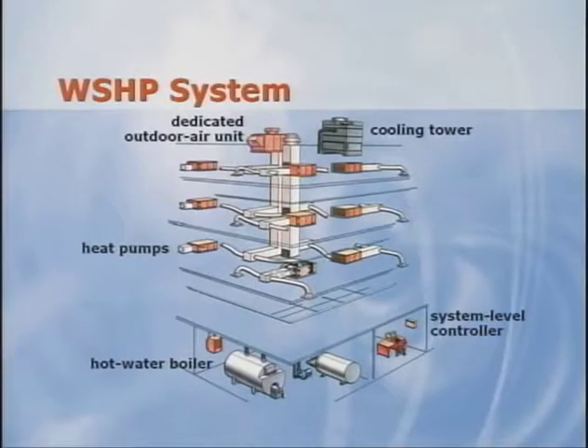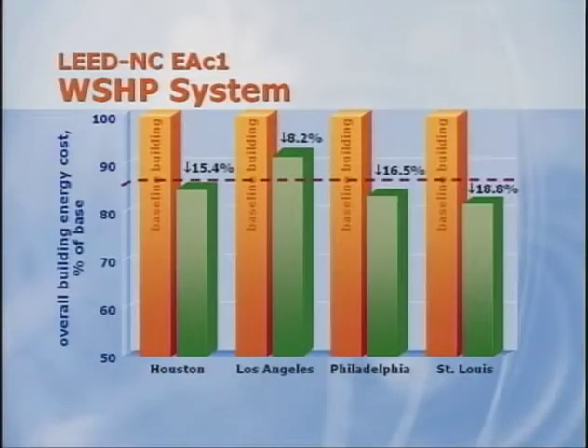Okay, next up is the water source heat pump system. In a conventional system, all the heat pumps are connected to a common water loop, along with a cooling tower and hot water boiler. Like in the fan coil system, a dedicated outdoor air system is used to condition all the ventilation air. Here's the chart comparing the proposed building with a water source heat pump system to the baseline building. The proposed building achieved 15% savings in Houston, 8% in Los Angeles, 17% in Philadelphia, and 19% in St. Louis. This system has some inherent energy advantages.